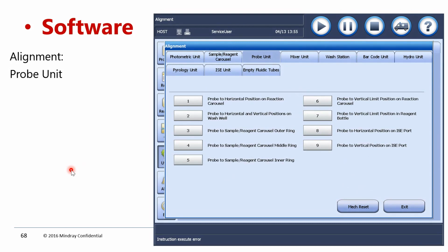So this is about the probe unit. For the sample and reagent probe alignment, you have different positions: rotation, and up and down. If you feel the probe is not correctly aligned, you have to go through the procedure step by step. For each position, whether horizontal or vertical adjustment is required, you have to increase or decrease the number of steps in the parameters.